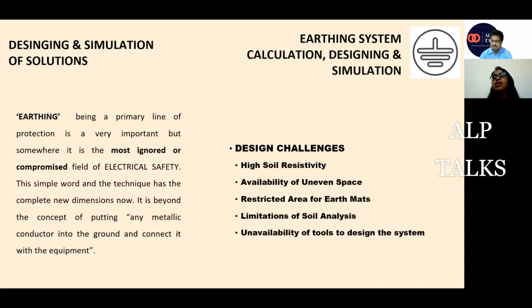So we should use the conductor material as per the soil resistivity and as per the fault current. Also, there was a misconception traditionally that we'll use 2 earthing pits only and our earthing is done. We do not require 4 pits, 5 pits, or 10 pits. But it is not so.